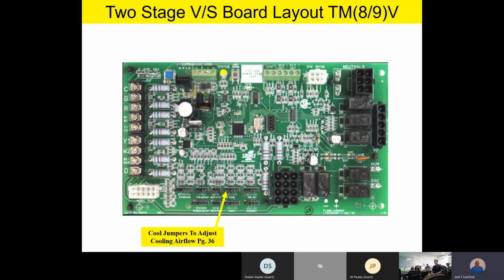If you have it hooked up to a single stage cooling unit outside, do not use the Y1 terminal, because if you use the Y1 terminal, it's only going to be 65% airflow on a Y1 call. We've actually had some contractors call in and say, "Hey, I'm not getting my full airflow on my unit outside." Well, what terminal did you use for your cooling call? "Well, Y1, because I got a single stage unit outside." No, don't use Y1 at all if you have a single stage unit outside.